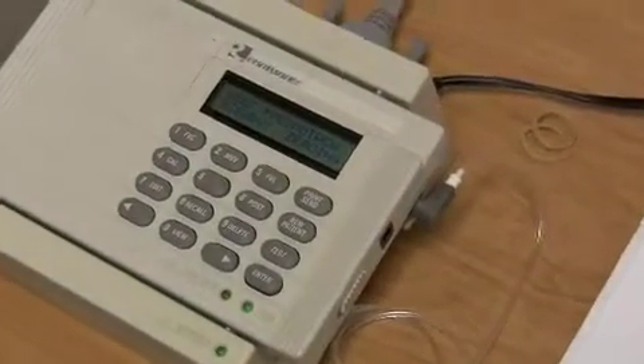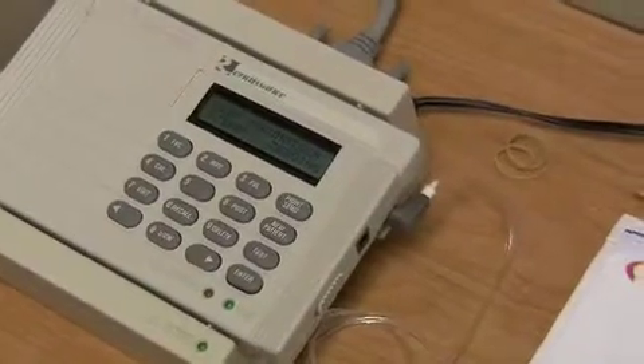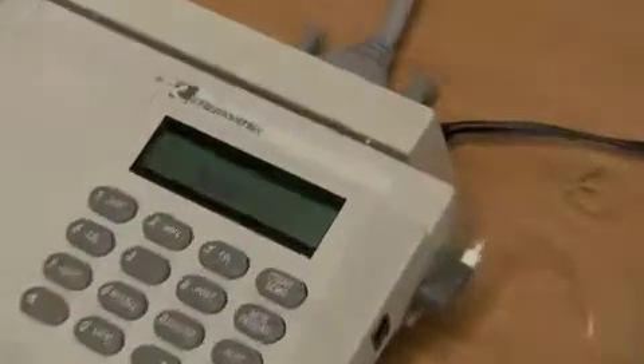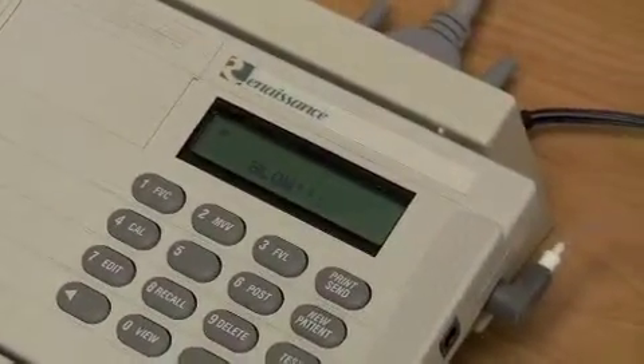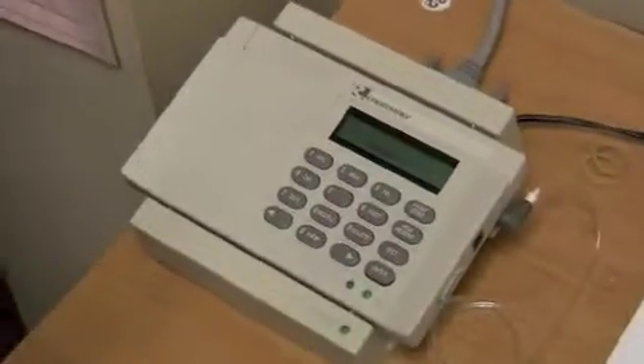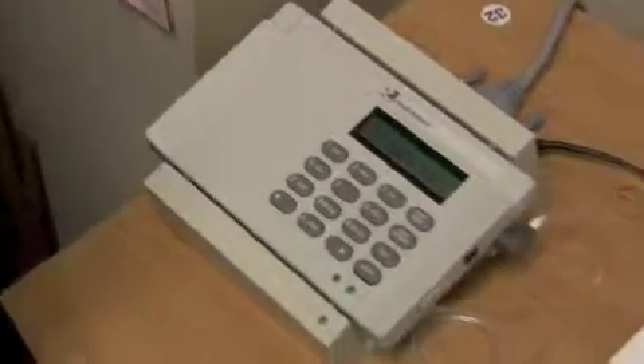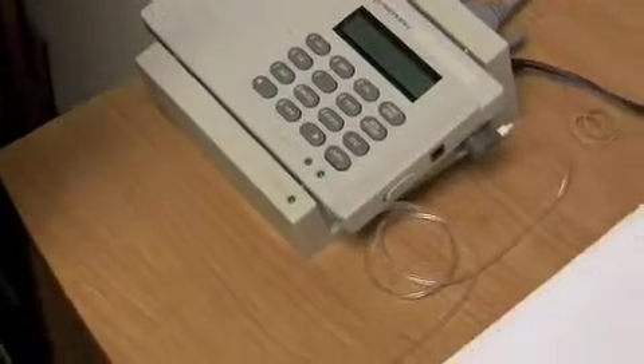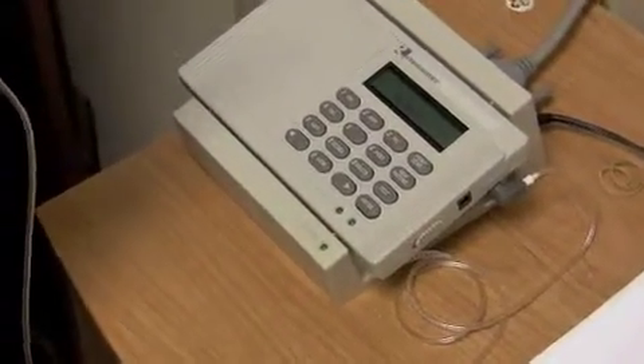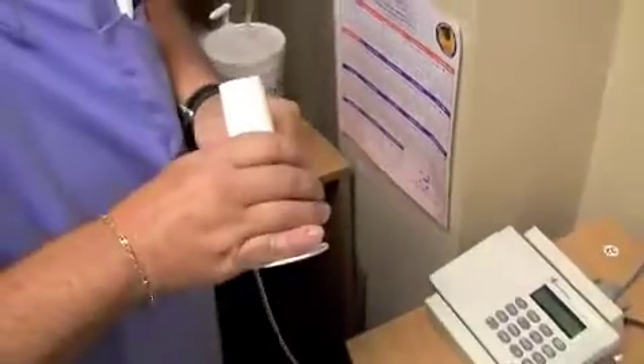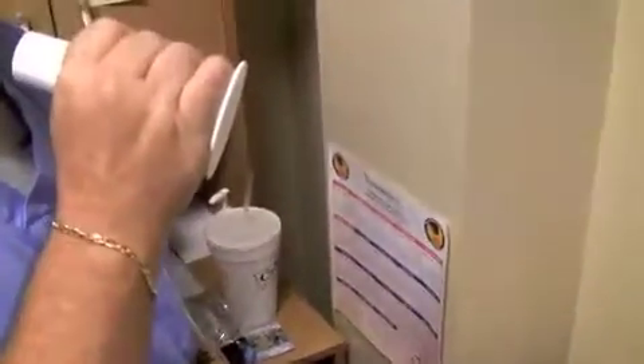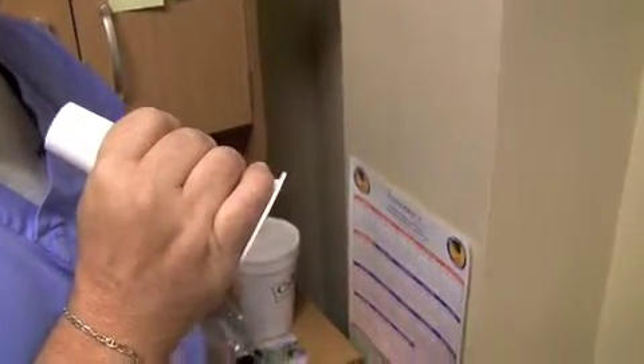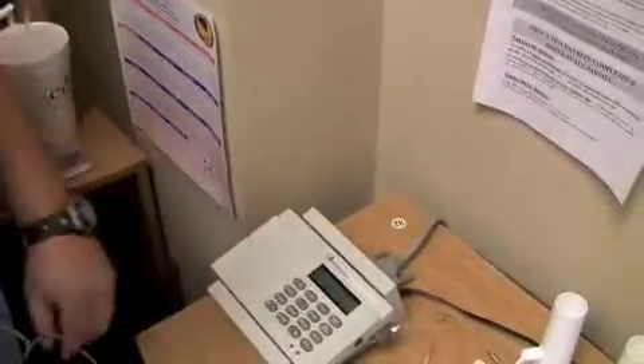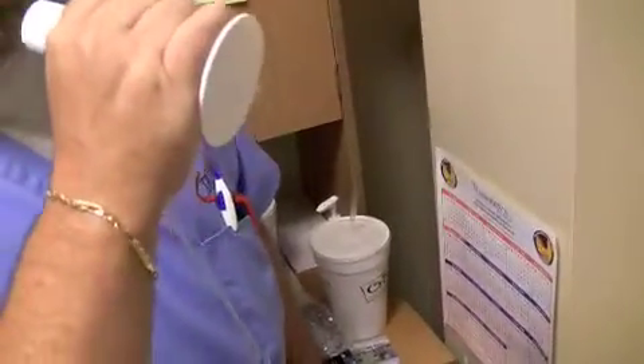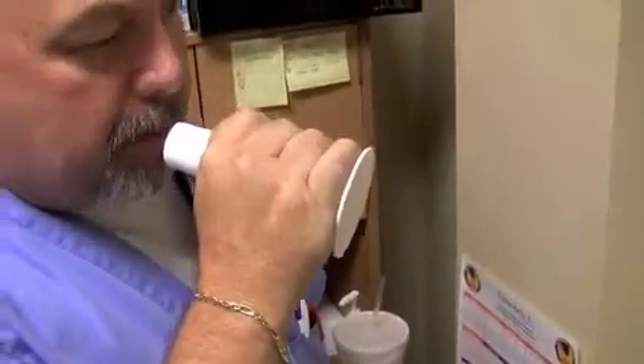Now at this point the machine is saying keep pneumotach steady, and it's zeroing. Then the machine is going to say blow. What I would recommend, before you actually initiate the test, is have the patient give you a couple of big breaths to clear out their lungs, especially if they are smokers. Of course, they are standing. Give a couple of cleansing breaths and have them stand at the ready with the mouthpiece close at hand.